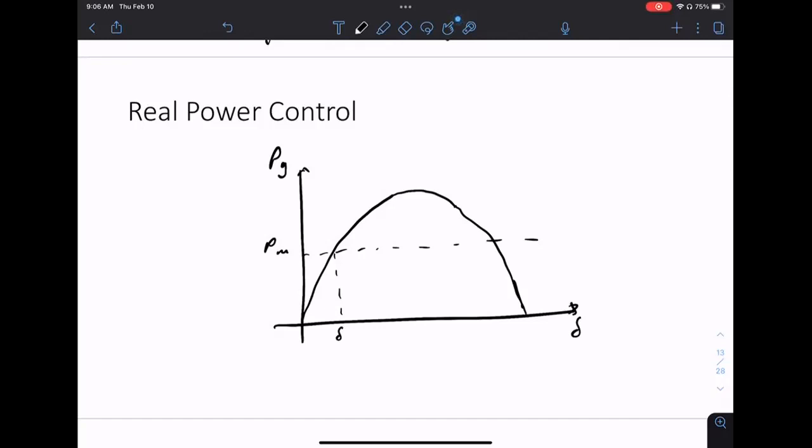No, so the small angle, right? There's a reason why we want to operate here. This is not too bad for small angle operation because it doesn't destroy the small angle approximation. It's linear here. It's sort of flat here. But this has to do with stability. You just want to pick this solution. And so again, if you're an operator sitting in a control room, if your angle ever gets to say 20 degrees, there'll be warning lights flashing all over for large angle. You see a lot of red lights flashing for this. So that's something to pick there.